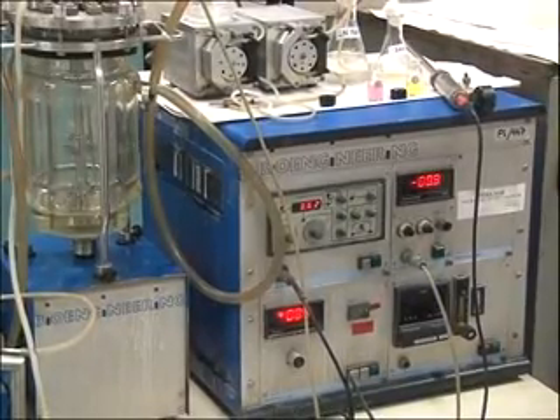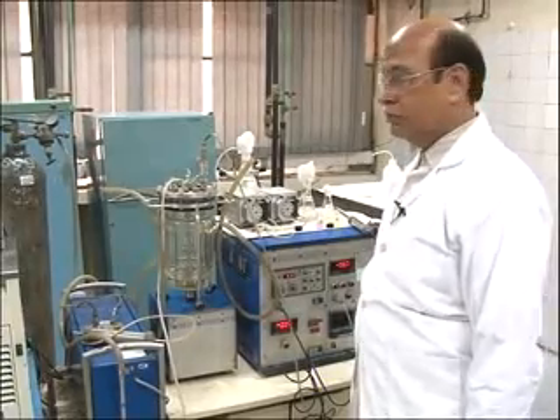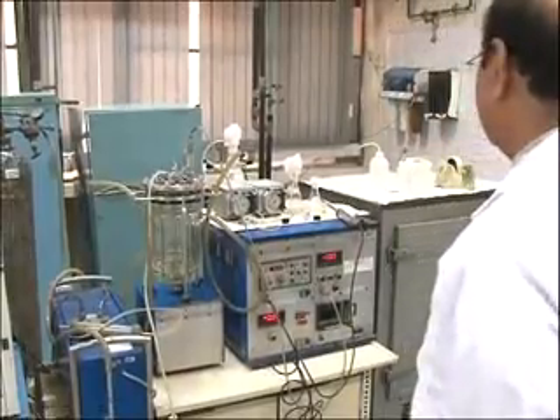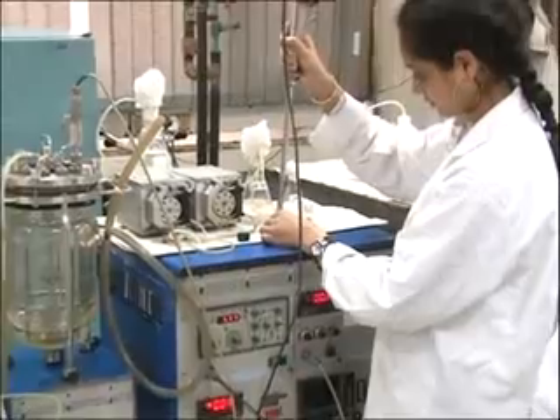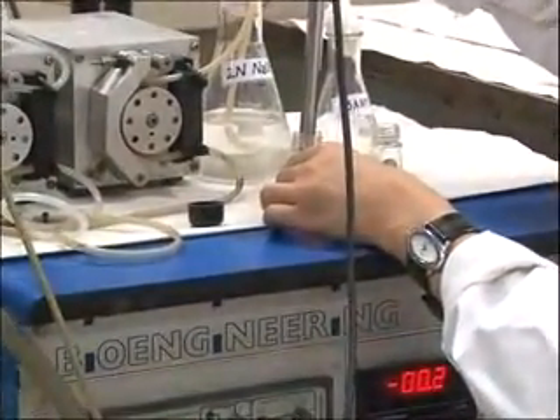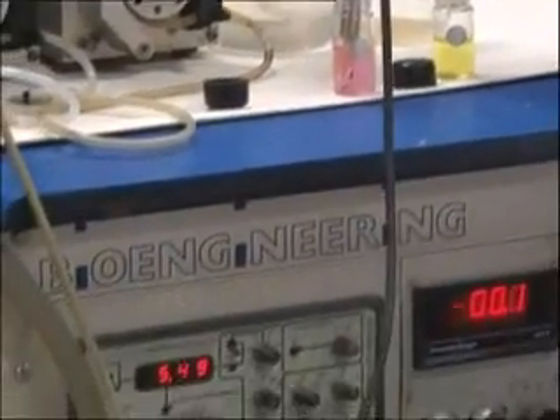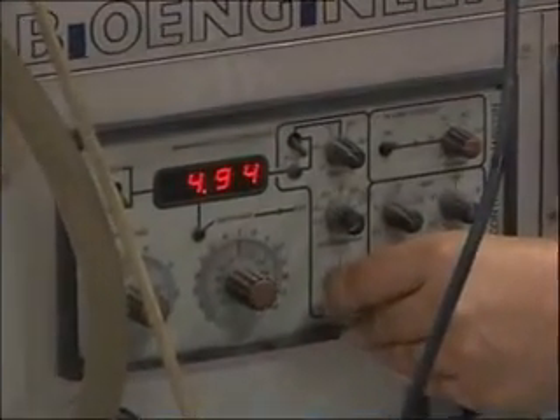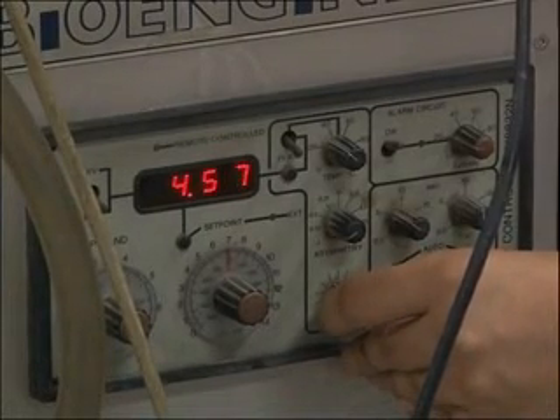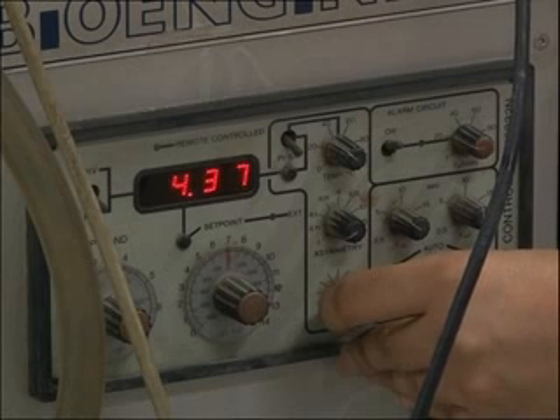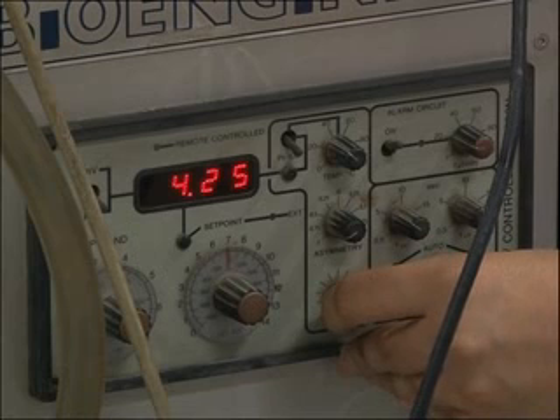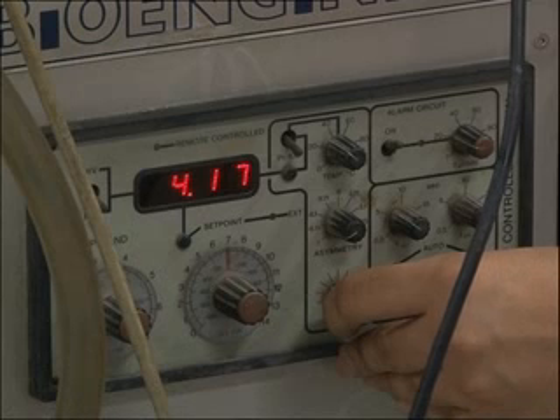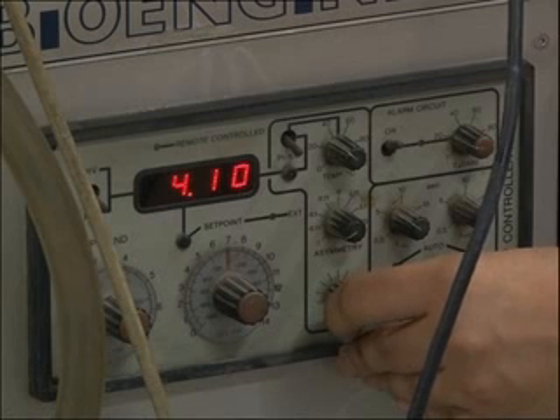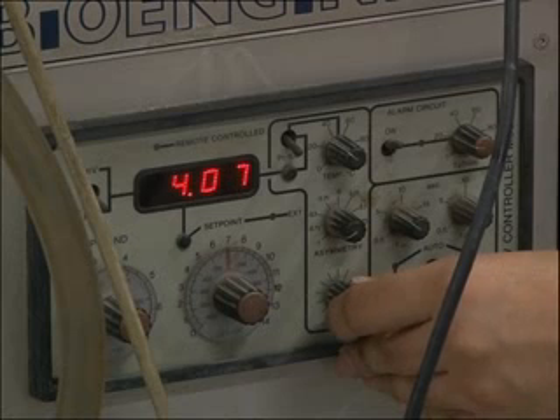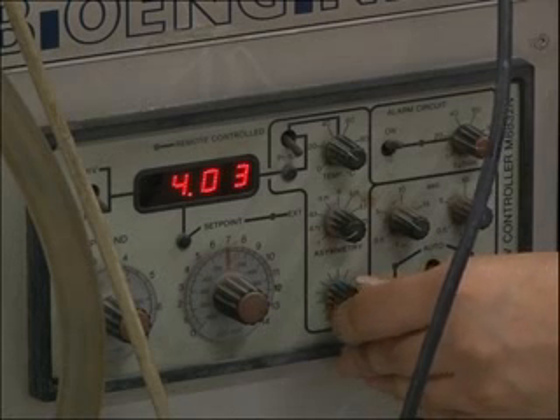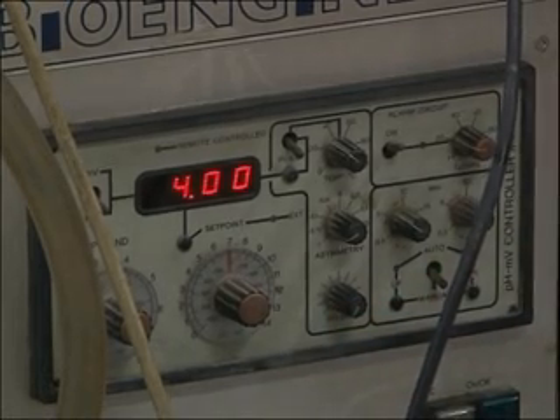So I'd like to demonstrate first the control of pH, so we start the calibration of the pH probe. First the probe is dipped into pH 4 buffer, as you see over here, and the reading should come as pH 4 here. If it is not coming, we will just make it 4 by the millivolt pH potentiometer knob, as you see over here. So now pH is adjusted to 4.